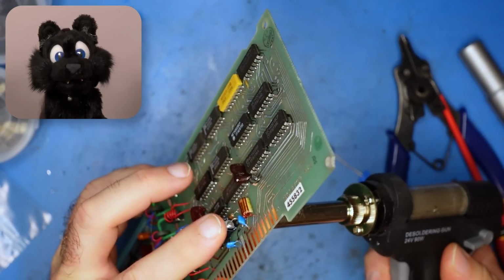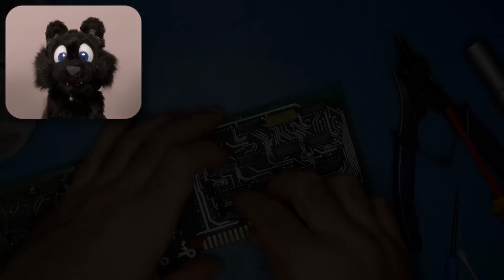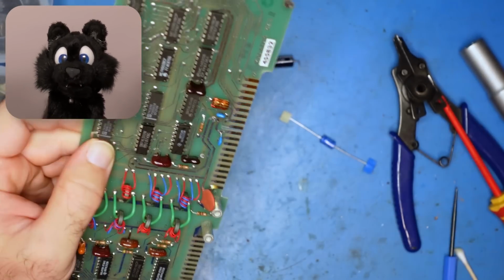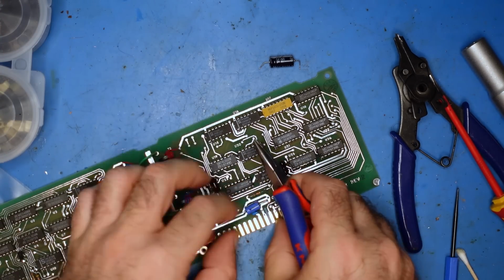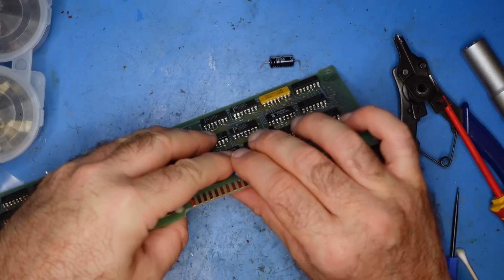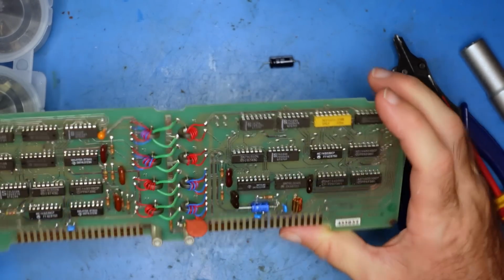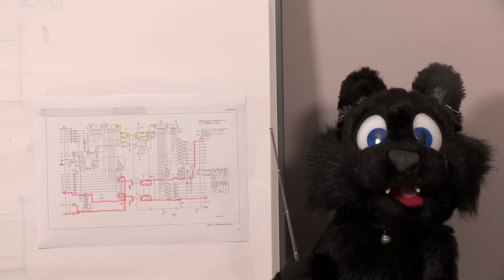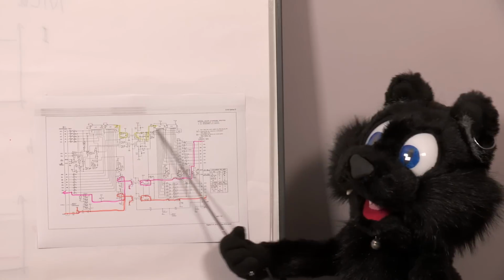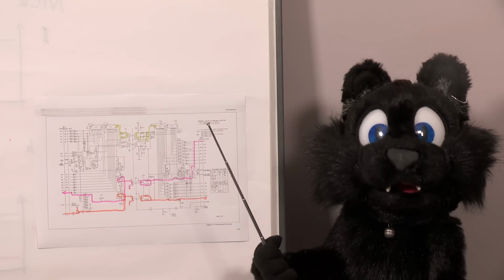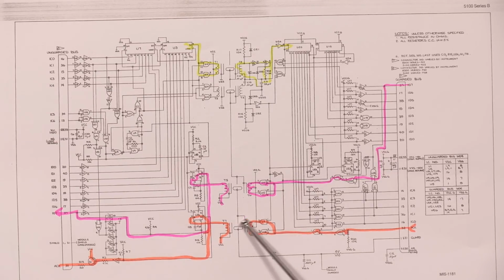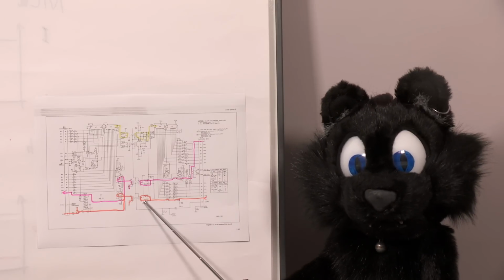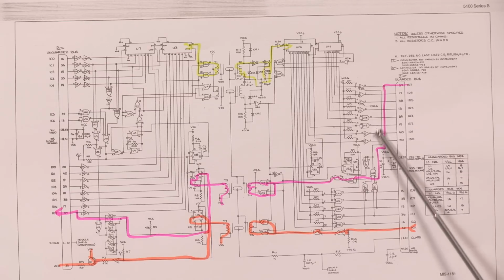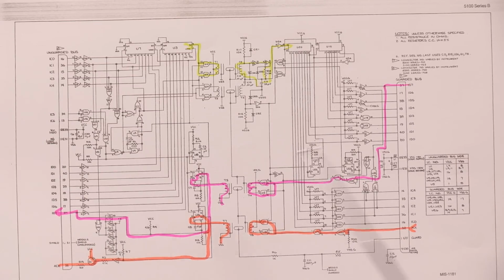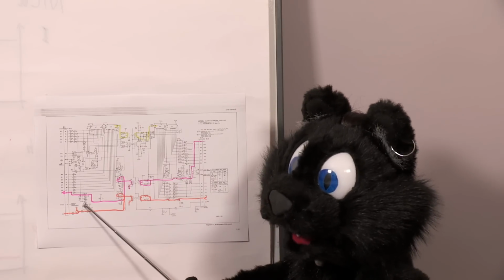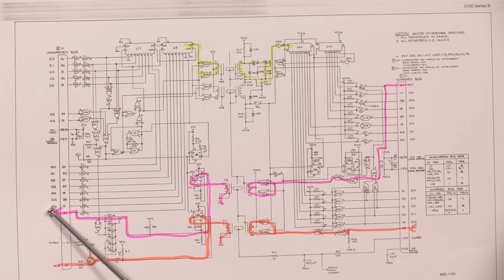Up next for recapping, the isolation board. It takes the digital control bus on one side and transfers data and address bits over to the instrument bus. This is done with a clock and a shift register, so 2 transformers take care of that. The addressed instrument card takes the bits and sends back an ACK signal for the CPU. This is the 3rd transformer. And the 4th? That one carries the overload line from the instrument bus back to the digital one. It's a weird combination. ACK is basically mapped to the interrupt line on the CPU, while the overload one is mapped to the MSB on the data bus.